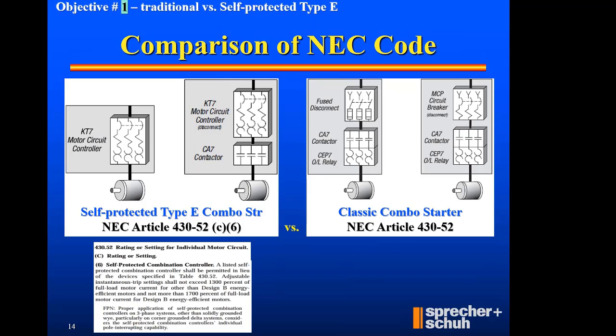So let's finish up with code and say, what were those code articles that we were talking about? On the right-hand side of the page, the illustration up here has a fuse disconnect feeding the contactor, feeding an overload. That's a classic combo starter. Article 430-52 gives us those justifications. And then additionally, with an MCP, there's my means of disconnect, there's the magnetic armature on the inside, there's the contactor, there's the overload. So that is a classic combo starter.